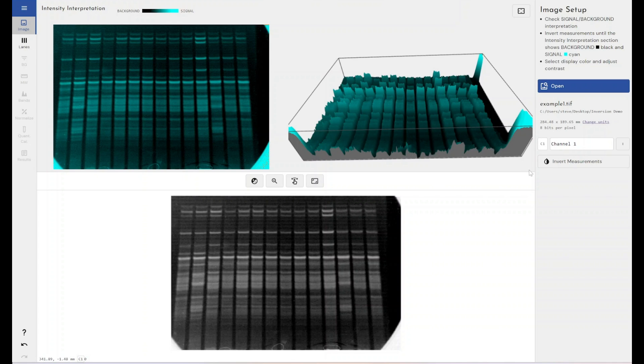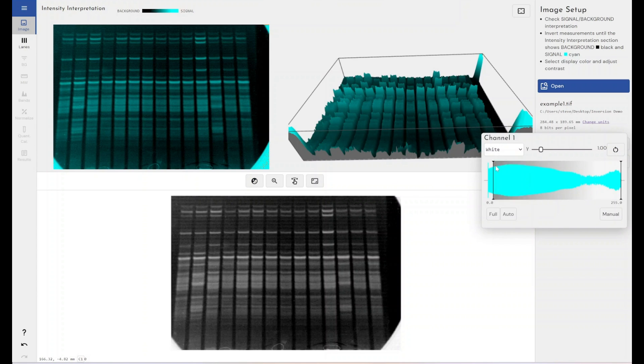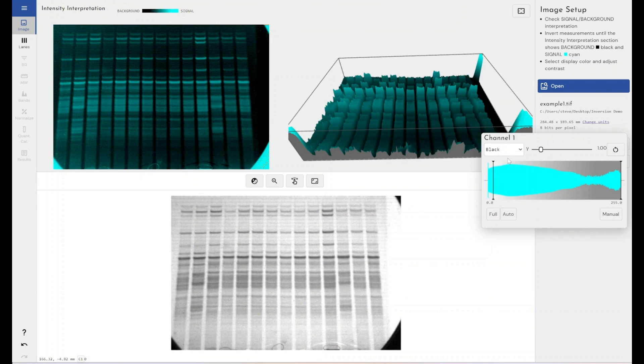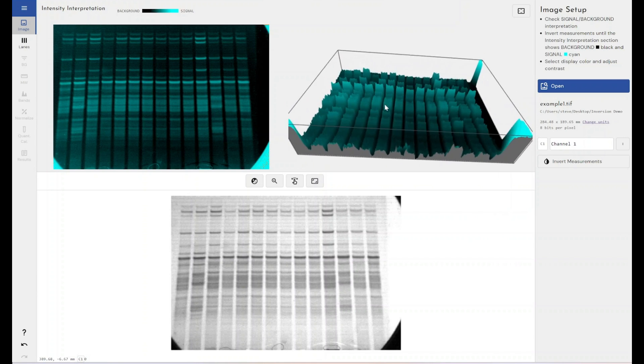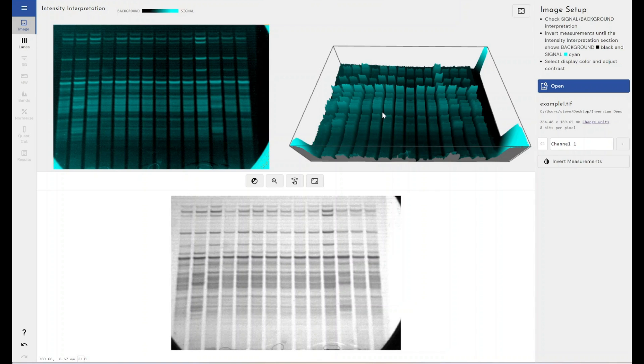However, what you can do is then just change the colorway. If you select a different color map, it will flip the colors to match what you expected to see, what you saw on capture. But the actual image measurements, the raw values, the pixel values remain the same. So it's this concept of, previously in our older software and in all of our competitors' software, the word invert has been used to just flip black and white. Within our software, we treat that as two separate things. Do you want to change the way the data is, or do you just want to change the way the image looks without changing the data?